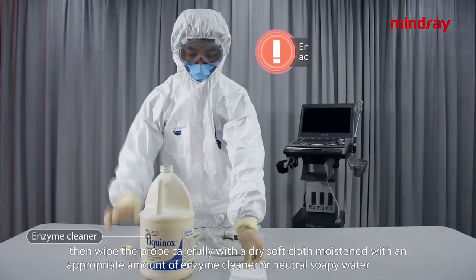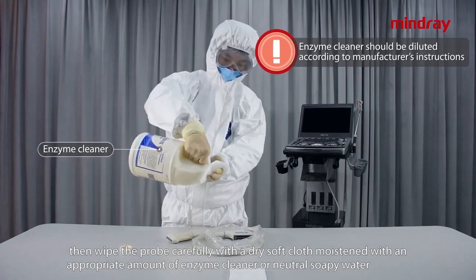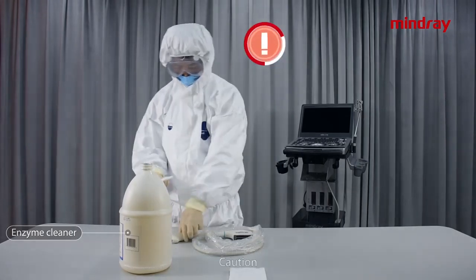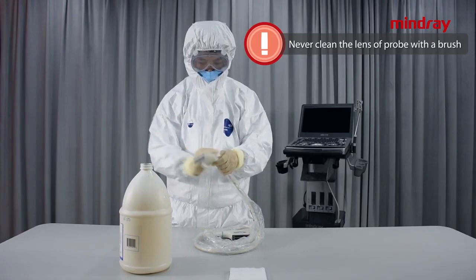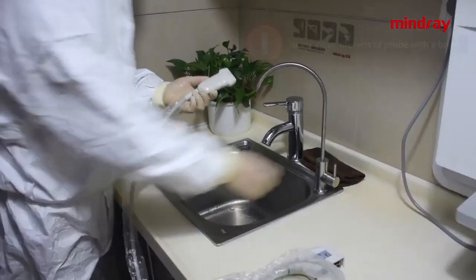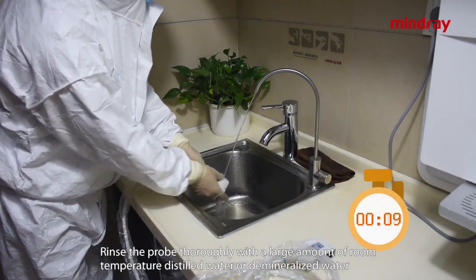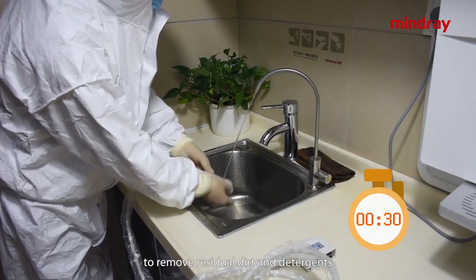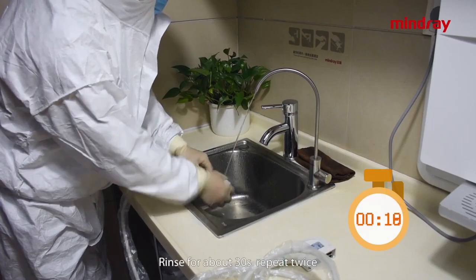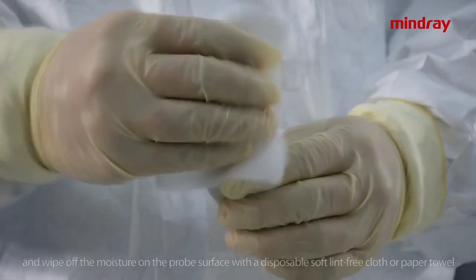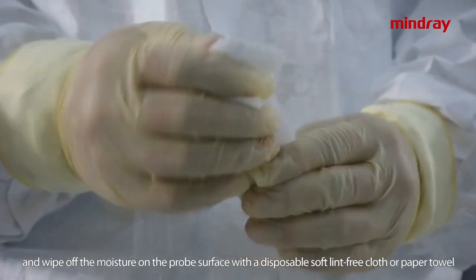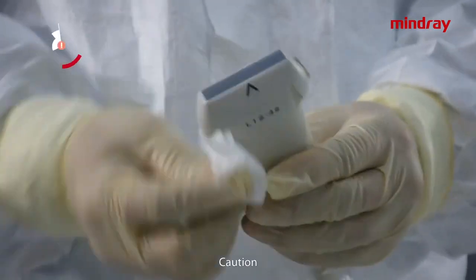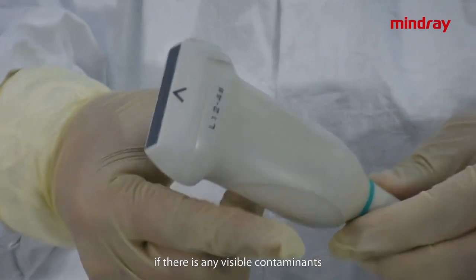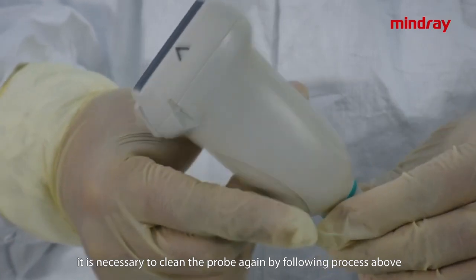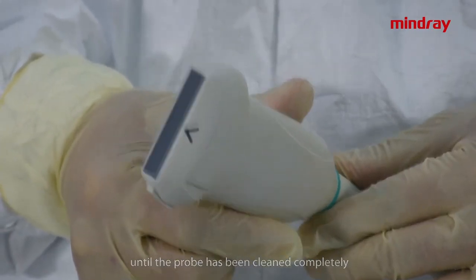Then wipe the probe carefully with a soft dry cloth moistened with an appropriate amount of enzyme cleaner or neutral soapy water. Caution: never clean the lens of probe with a brush. Rinse probe softly with a large amount of room temperature distilled water or demineralized water to remove residual dirt or detergents. Rinse for about 30 seconds. Repeat twice, and wipe up the moisture on the probe surface with a disposable soft, lint-free cloth or paper towel. Caution: never dry the probe by heating. Check the probe. If there is any visible contaminants, it is necessary to clean the probe again by following process above until the probe has been cleaned completely.